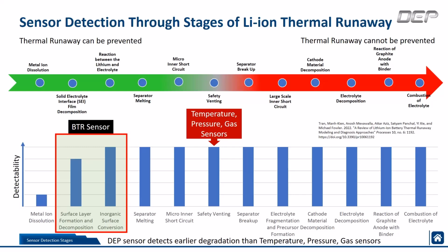Every point before the safety venting, it is possible to mitigate and even prevent the thermal runaway. After safety venting, it becomes much more difficult to mitigate, let alone prevent. It becomes a very difficult and almost impossible scenario. So our sensor actually detects within these first three stages, more so the second two, where we get a very early detection of the thermal runaway, much earlier than existing sensors now, which detect at the safety venting, where all the gases end up escaping the prismatic cell and reach the gas sensors or the pressure buildup. Temperature detection can also be late.